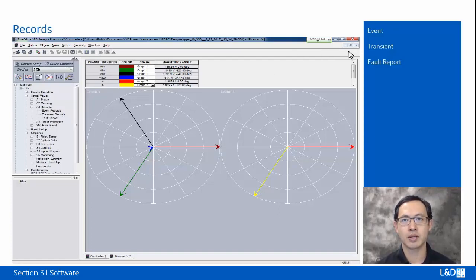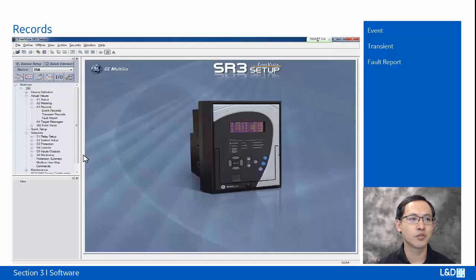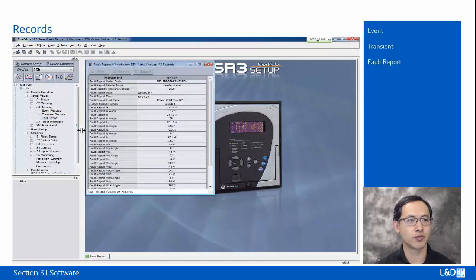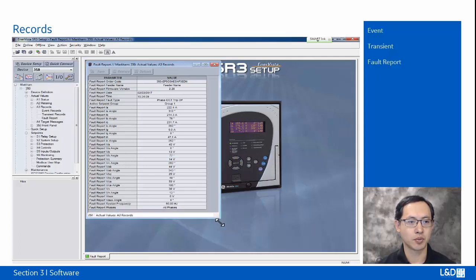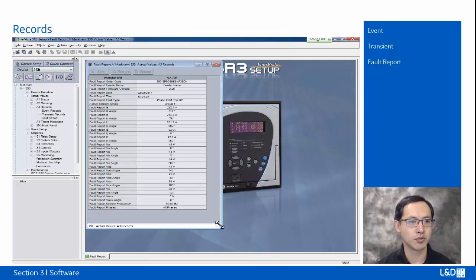And the last one is the fault report. We can only launch the fault report from the menus, actual values, A3 records. There's no shortcut, and from this fault report, we can see more detailed information on the type of the relay, order codes, version numbers, the fault date, and what type of the fault. So it's much more information than the event recorder.